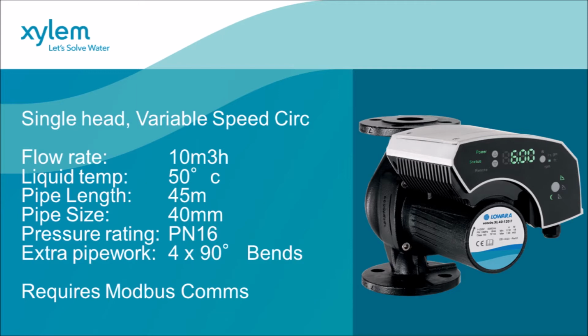For the first example, we have been asked to make a selection for a heating circuit. We require a single head variable speed circulator. We have been advised that the flow rate has been calculated at 10 cubic meters per hour. The water temperature is 50 degrees Celsius. There will be 45 meters worth of new galvanized steel pipework with 4 90-degree bends. And finally, we have been asked to include external communication via Modbus.